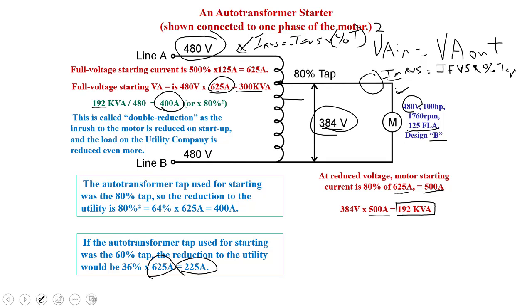Now we have to keep in mind the type of load we're starting. Once again, whether it's a variable torque load or a constant torque load, and how the motor is sized. So we have to be cautious when doing this, that we are actually able to still start the load. Because when we look at it, the torque that this motor produces during startup, its full voltage starting torque, is also reduced in proportion to the square of our voltage reduction.